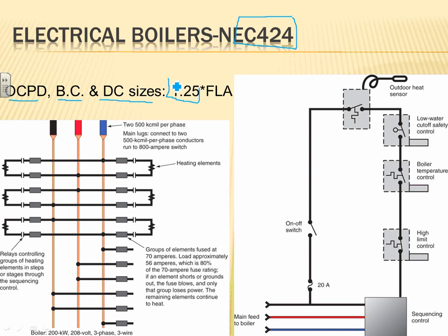And by boiler here, I mean an electric boiler, an electricity-burning boiler, meaning not a gas boiler, powered with a 20 amp control circuit for it. These are burning electricity to boil the water. So here's an example of this one. I have this baby typically, so I have two runs of, I don't know what the overcurrent protection device is. My overcurrent protection device coming in here, I could have an 800 amp feeder coming into that boiler. Do you guys do a lot of electric boilers, burning electricity? Not a whole lot. But if you were to use one, here's an 800 amp feeder coming to the boiler. That's where you can split them into two 400s coming into that system, fed via two sets per phase.